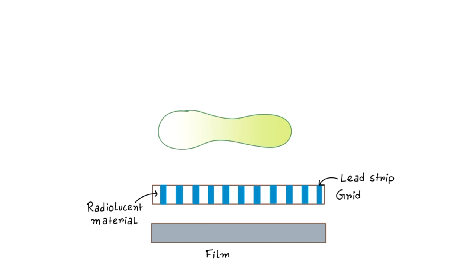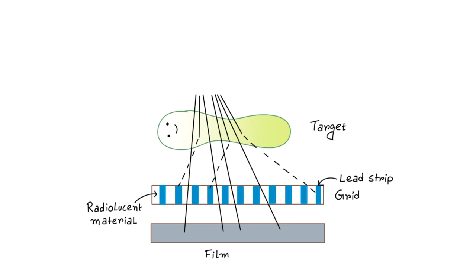Now after penetrating the target object, primary beams pass through this small gap between the lead strips and fall on the radiographic film. However, the scattered photons move obliquely and strike the lead strips at an angle and get absorbed by them.